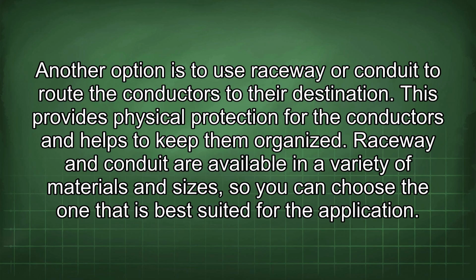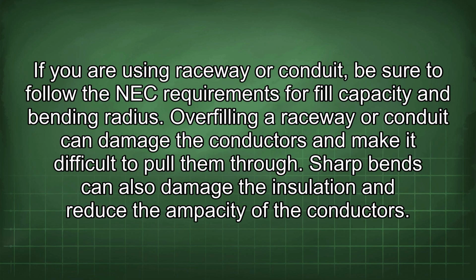Another option is to use raceway or conduit to route the conductors to their destination. This provides physical protection for the conductors and helps to keep them organized. Raceway and conduit are available in a variety of materials and sizes, so you can choose the one that is best suited for the application. If you are using raceway or conduit, be sure to follow the NEC requirements for fill capacity and bending radius. Overfilling a raceway or conduit can damage the conductors and make it difficult to pull them through. Sharp bends can also damage the insulation and reduce the ampacity of the conductors.